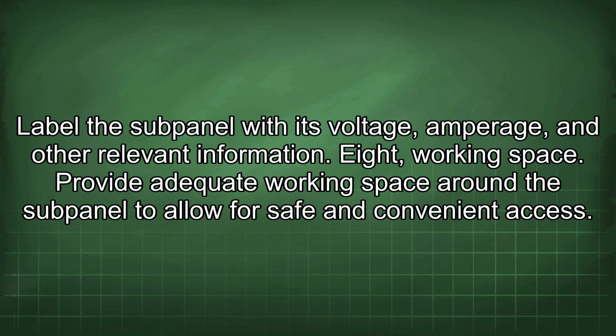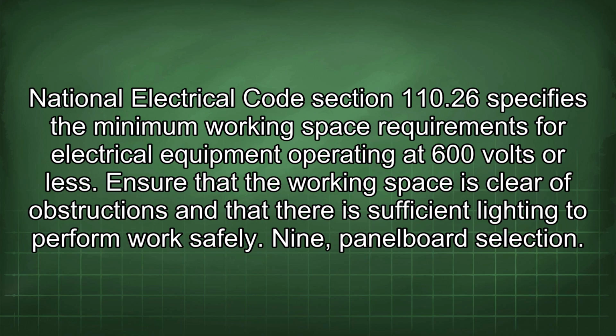8. Working space. Provide adequate working space around the subpanel to allow for safe and convenient access. National Electrical Code Section 110.26 specifies the minimum working space requirements for electrical equipment operating at 600 volts or less. Ensure that the working space is clear of obstructions and that there is sufficient lighting to perform work safely.